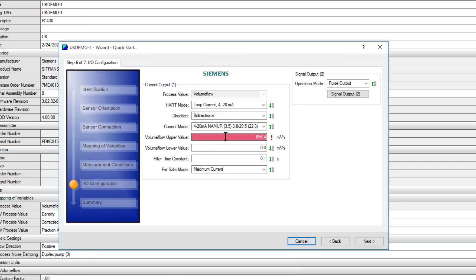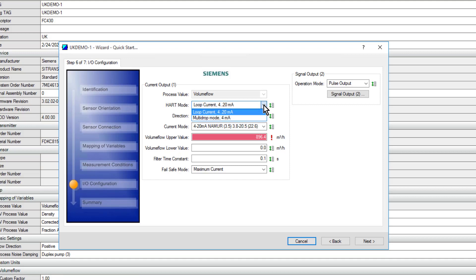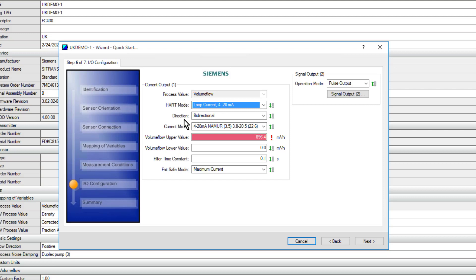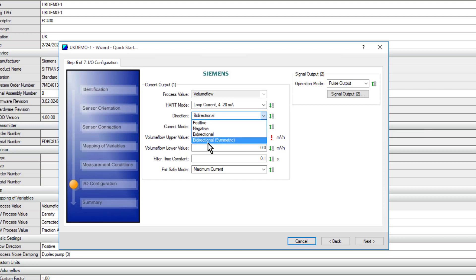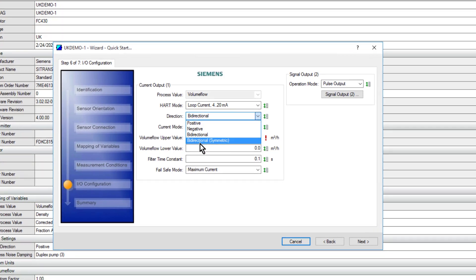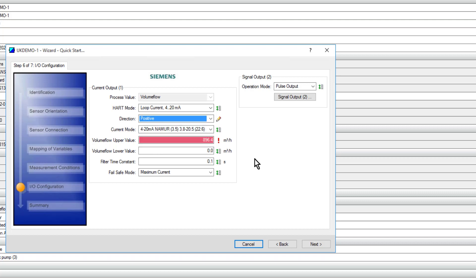Next, volume flow. You can see there it has got an issue, so just have a look at this. Loop 4-20. We can do multi-drop mode if we want. Then under here, positive or negative flow, and then we have bi-directional, and then we have this symmetric one where it does positive and negative flow over the full scale. Zero flow will be 12 milliamps for instance. We'll just set that for positive.